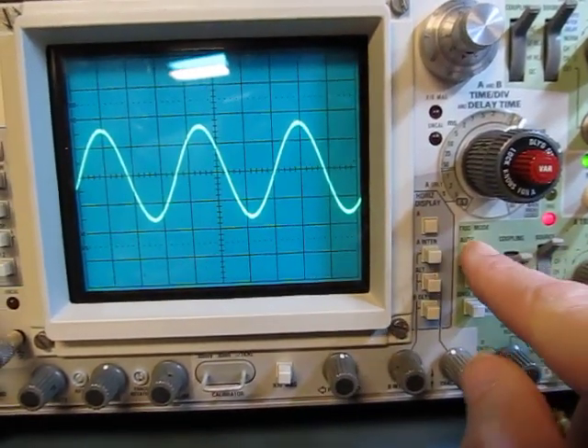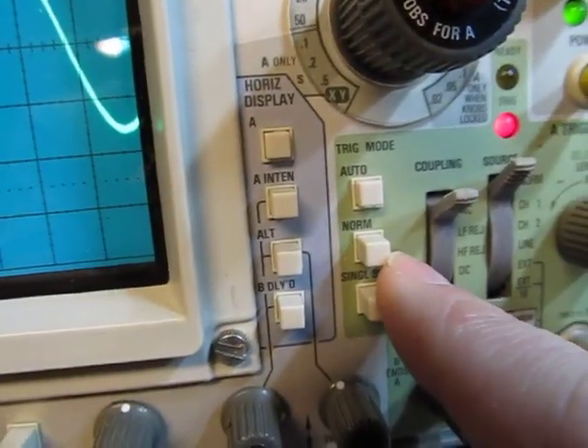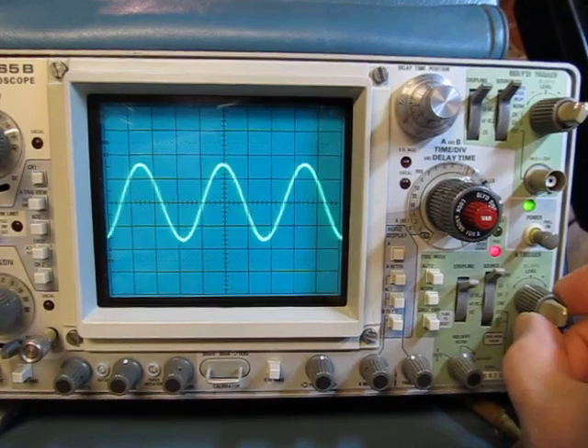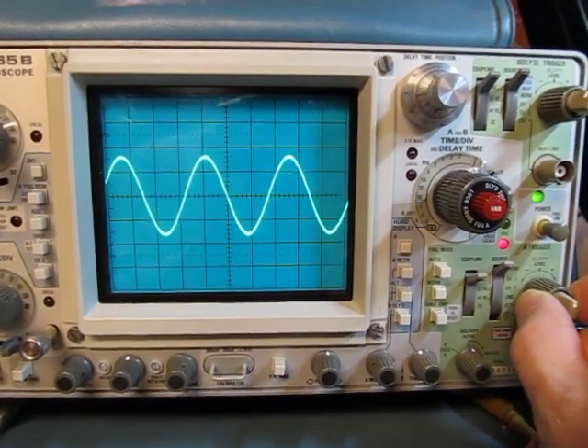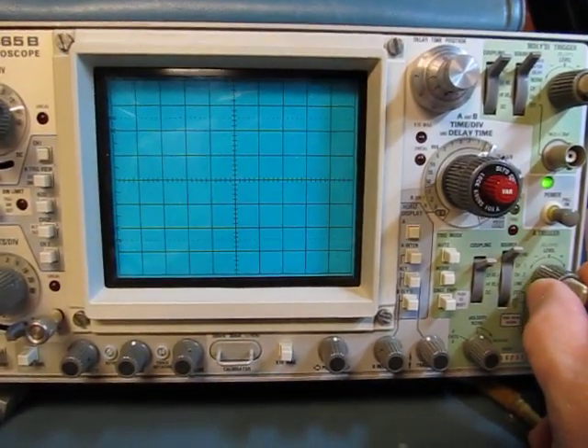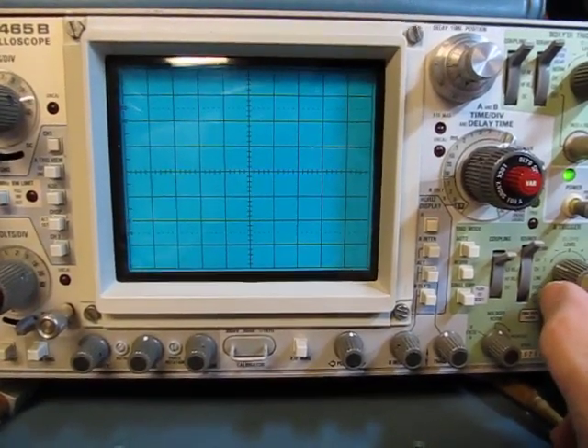Now, if I change the trigger mode from auto to the next one down here, which is normal, and we can see the display hasn't changed, and if I change the trigger amplitude, you can see that I can still move up or down, but watch what happens if I go too far below. The trace goes away.